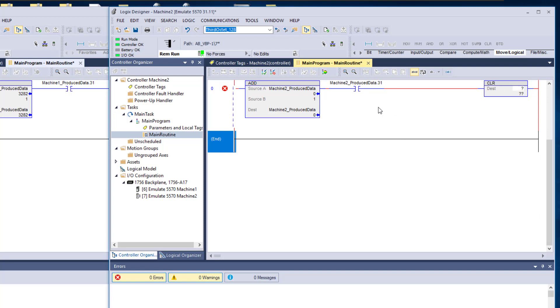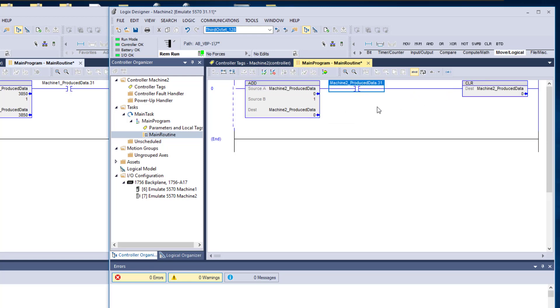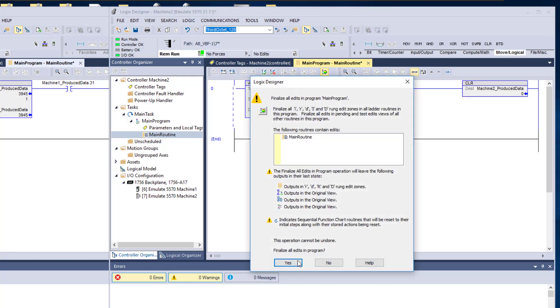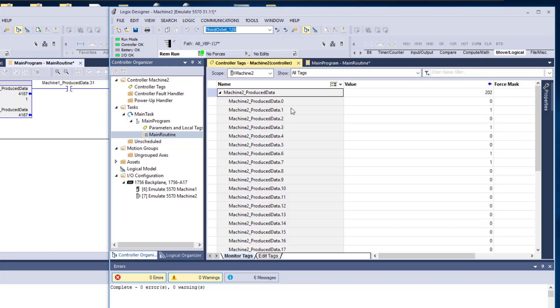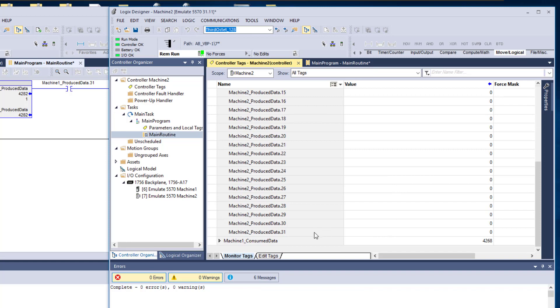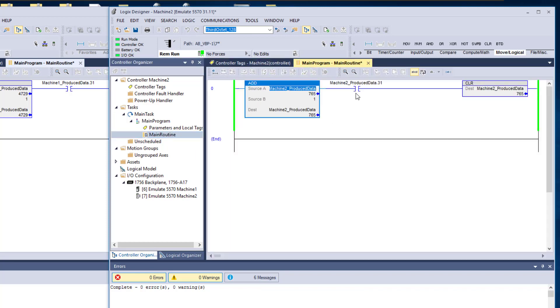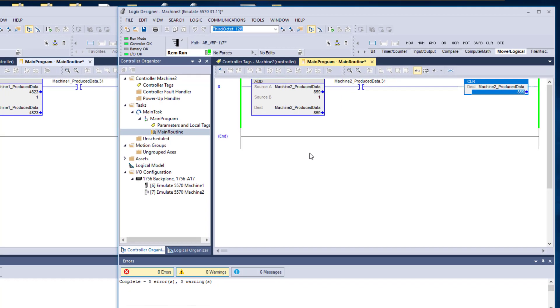Now when bit 31 comes up high, all it's saying is that you've filled up all your data — all the data is filled up inside of that DINT. When the DINT data fills up to value 31, that goes high, meaning you're filled out. The binary of that specific instance is being used, and as soon as that's being used, we want to clear the data to reset it.